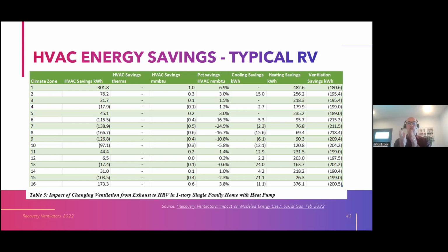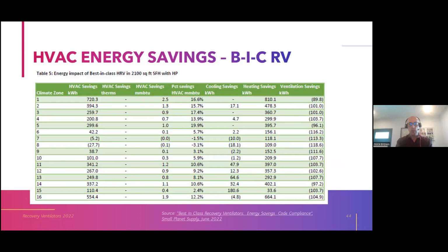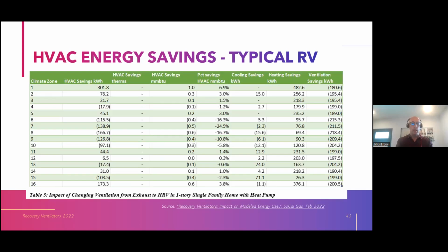But we've got heating savings and cooling savings in some climate zones. So the HVAC savings kWh in the second column is the sum of these other columns. This is the bottom line. And so you see climate zone 1, 2, 3, 5, 11, 12, 14, 16 with savings. You see that? And on a percent basis, yeah, 3, 7. It was a little better in the furnace chart. But thank you, Sarah. She put a link to the study in your slide deck, so you can look into it in more detail.